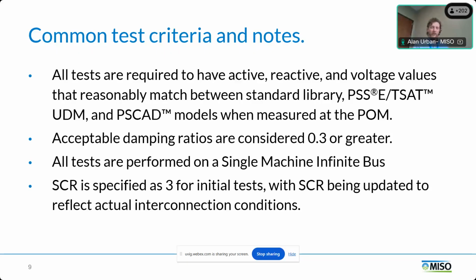We defined acceptable damping ratios to be 0.3 or greater, and that is, I think, right out of 2800. All these tests are performed on a single machine infinite bus. We also specified an SCR for the majority of these tests at 3, which was right on the line between what's considered high SCR and low SCR. The intention is that the SCR gets updated once we understand what the actual interconnection conditions are at the point of interconnection. So we can update it to higher than 3 if that's what's actually out there, or if it has to be lowered, that will help us identify issues in low SCR conditions.